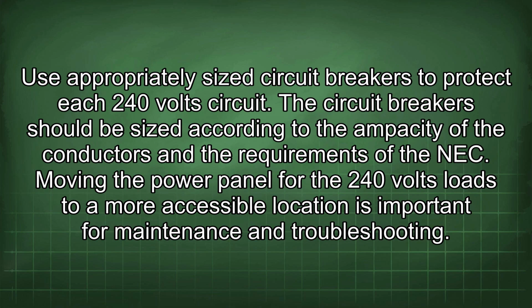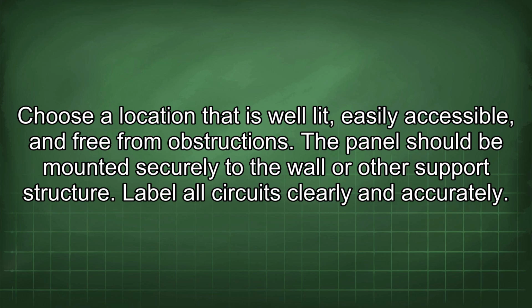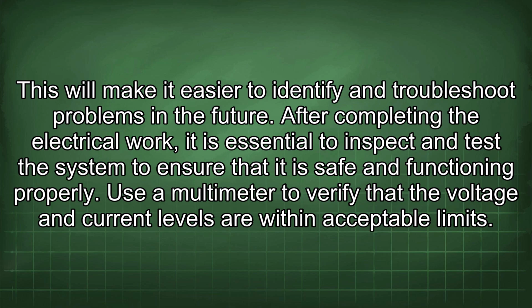The circuit breakers should be sized according to the ampacity of the conductors and the requirements of the NEC. Moving the power panel for the 240 volts loads to a more accessible location is important for maintenance and troubleshooting. Choose a location that is well lit, easily accessible, and free from obstructions. The panel should be mounted securely to the wall or other support structure. Label all circuits clearly and accurately. This will make it easier to identify and troubleshoot problems in the future.